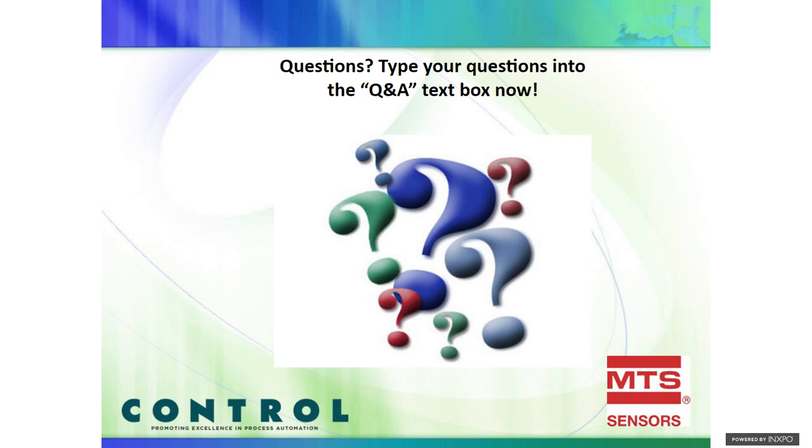So we've had a lot of customers come back and say, well, this isn't from CSA or this isn't from UL. Is it still safe? Is it still usable? And the answer is yes, as long as you're getting a certificate from one of the recognized bodies. In the U.S., it would be an NRTL, a nationally recognized testing laboratory, or under ATEX, it would be called a notified body. As long as you're getting a certificate from one of these agencies that is recognized and approved, then there is no difference in the safety of that product.